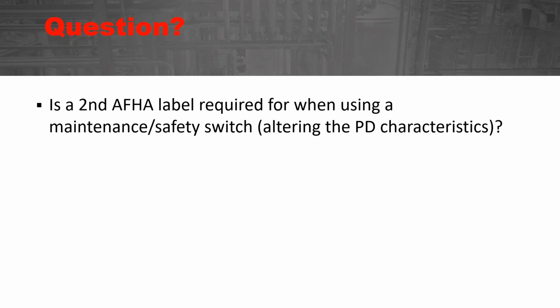Commonly, I do see a second label on equipment that says label A is for normal operation and label B is only when the equipment is put into maintenance mode. So is it required? I'd say unlikely unless you are increasing incident energy, but I do see it as a common industry practice that people will add a second label on their equipment if they have the maintenance mode capability. Okay. Sounds good. So let's go to the next question.